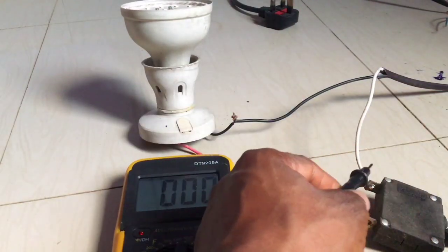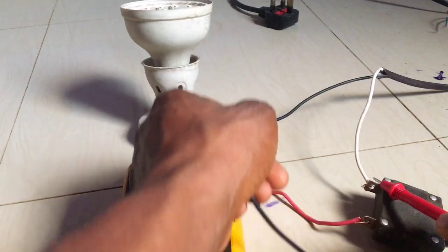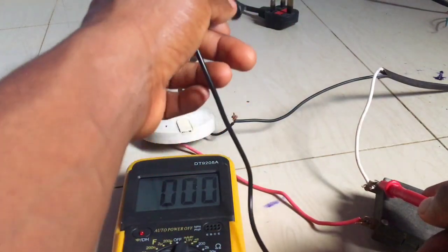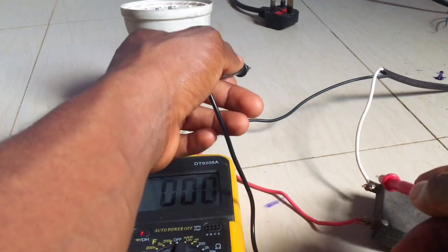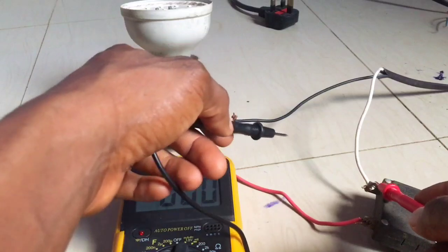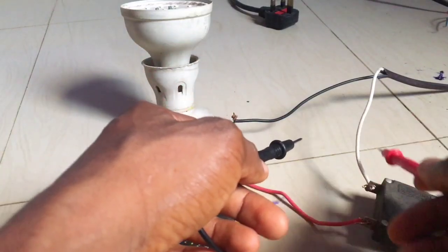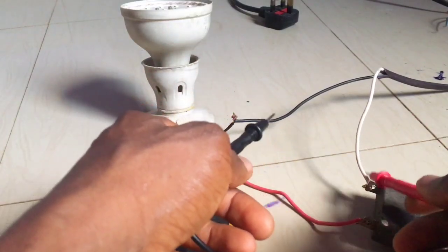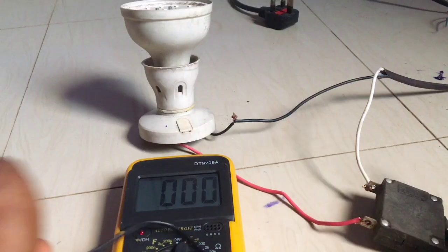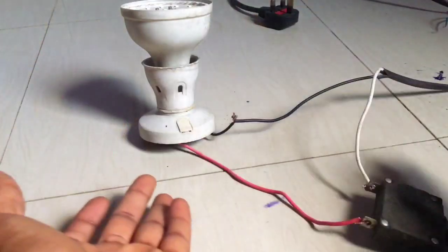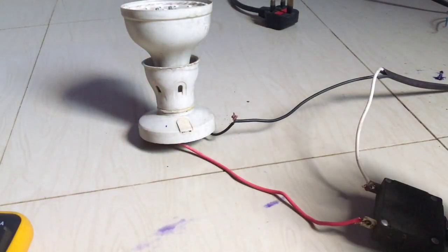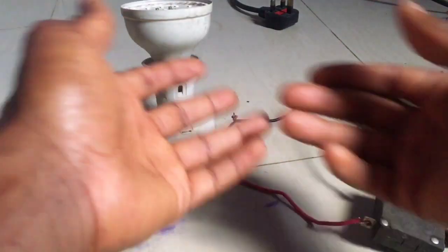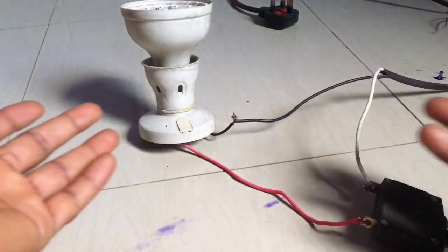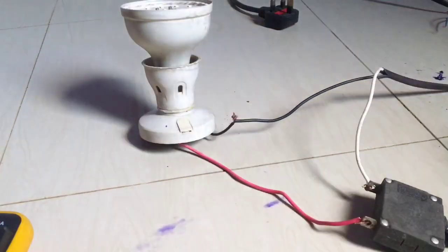To test the live link, if it's bad, you place one probe here and look for neutral anywhere. If you don't get voltage across this line and any other functional neutral line, then you know that this very cable is faulty. It's not energized, so you trace where it is supplied from. So this is just the conduit wiring. Whether you have a conduit wire building or a surface wire building, you can know your way around issues that have to do with switch connection or your lamp holder.